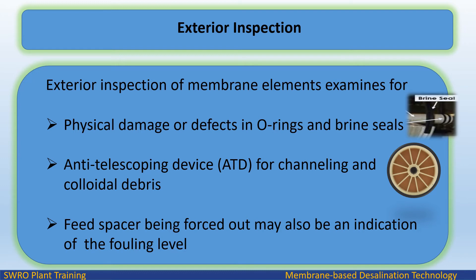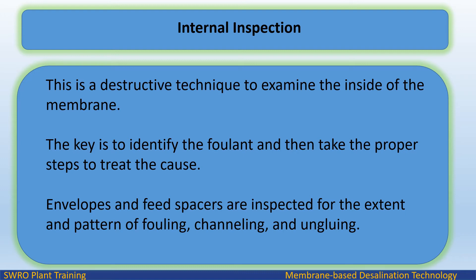Exterior inspection: The exterior inspection of membrane elements examines for physical damage or defects in O-rings and brine seals, the anti-telescoping device (ATD) for channeling and colloidal debris, and whether the feed spacer is being forced out, which may also be an indication of fouling level. Internal inspection: This is a destructive technique to examine the inside of the membrane. The key is to identify the foulant and then take the proper steps to treat the cause. Membrane envelopes and feed spacers are inspected for the extent and pattern of fouling, channeling, and ungluing.